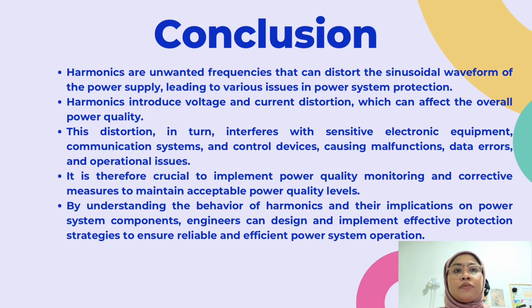So I will conclude this presentation. Harmonics are unwanted frequencies that can distort the sinusoidal waveform of the power supply, leading to various issues in power system protection. Harmonics introduce voltage and current distortion, which can affect the overall power quality. This distortion in turn interferes with sensitive electronic equipment, communication systems and control devices, causing malfunction, data errors and operational issues. It is therefore crucial to implement power quality monitoring and corrective measures to maintain acceptable power quality levels. By understanding the behavior of harmonics and their implications on power system components, engineers can design and implement effective protection strategies to ensure reliable and efficient power system operation.